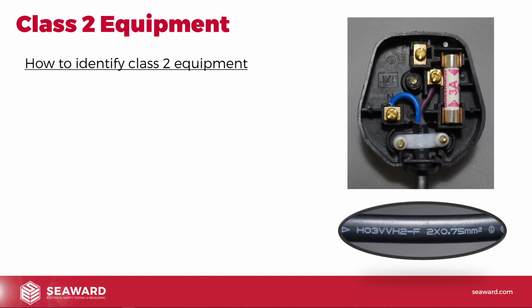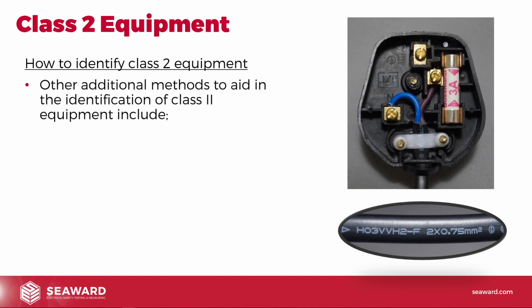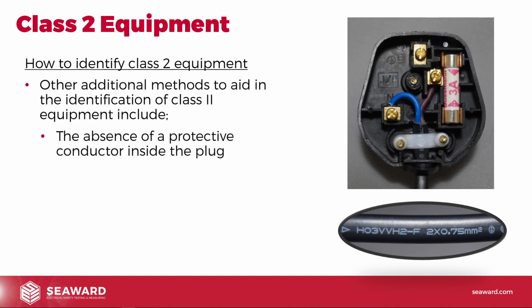Well again, going back to the logic we use with class 1 equipment, other additional methods to aid in the identification of class 1 or class 2 equipment include the absence of a protective conductor inside the plug. So if it's not a moulded plug and you can take the plug off, you look inside there and you can see there's no earth, there's no protective conductor. So generally you're thinking, well, that aligns with what I know about class 2 equipment.